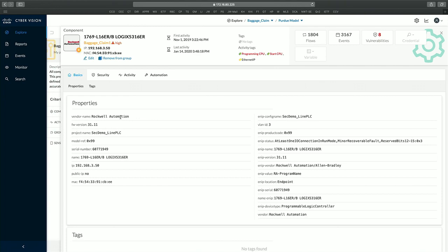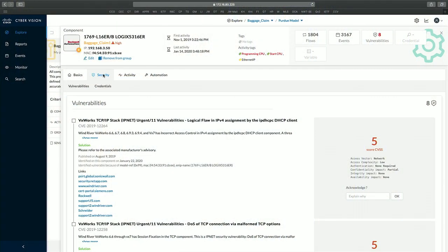We know every single device because the CyberVision sensor speaks the language of these industrial protocols — the devices announce themselves in their communication. We know the make, model, serial number, and firmware of any given device. For example, clicking on a Rockwell controller shows the list of known security vulnerabilities for that specific firmware version, so we can implement a plan to address those vulnerabilities and raise the security posture of the OT environment.